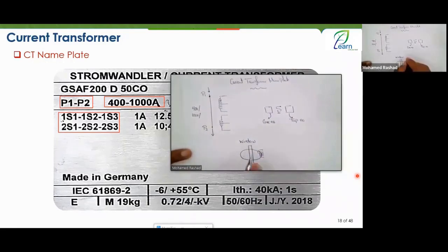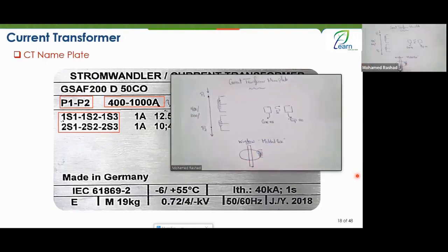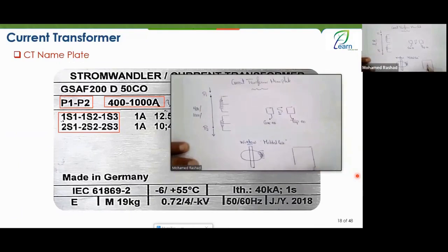Great, engineer. This type is sometimes referred to as having the core inside a molded case. The molded case, as engineers say, means that inside the same box there can be two iron cores. One could be for protection and the other for metering. Both could be for protection or both could be for metering. It means it's in a molded case, like a molded body or shell with the internal components inside.